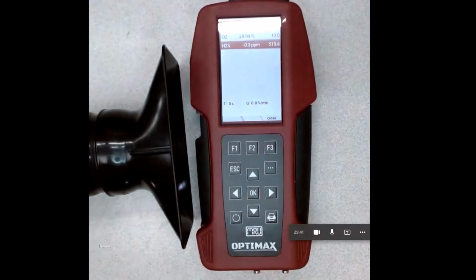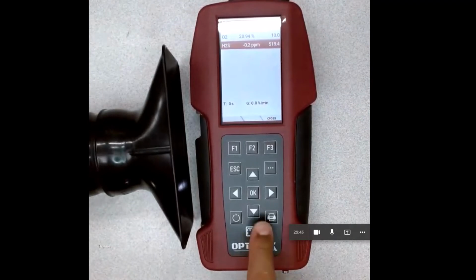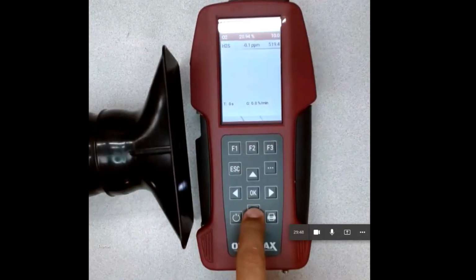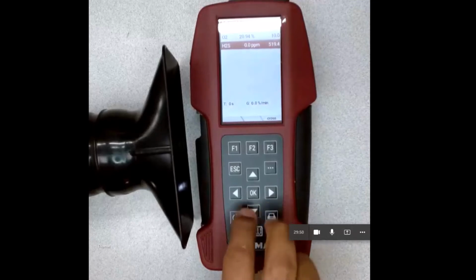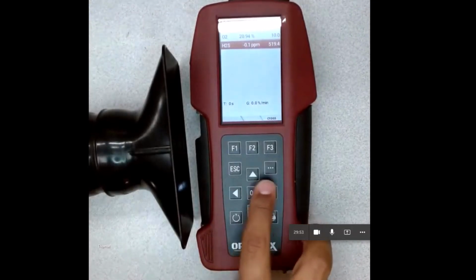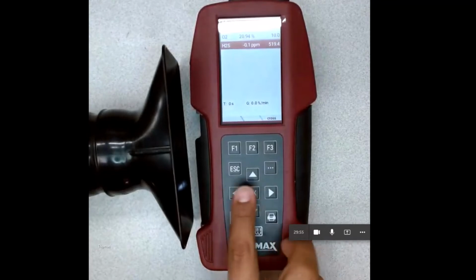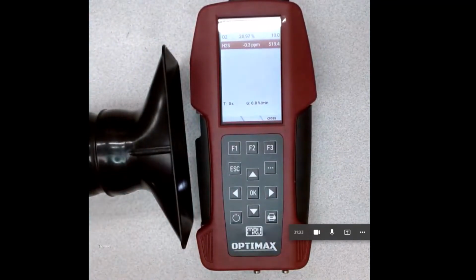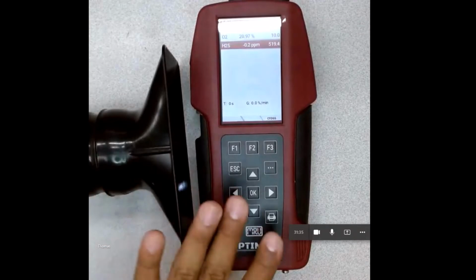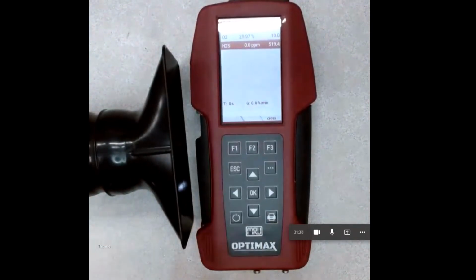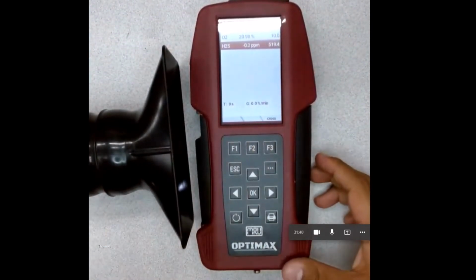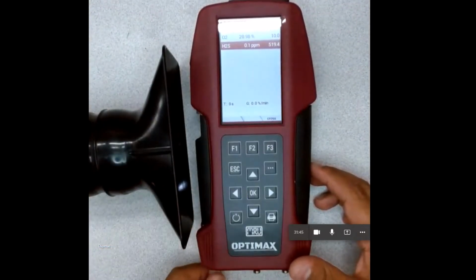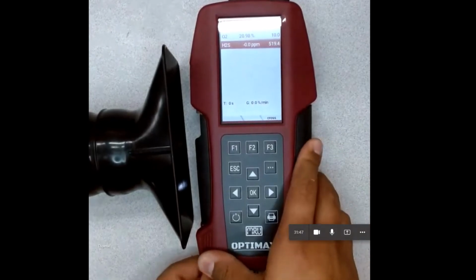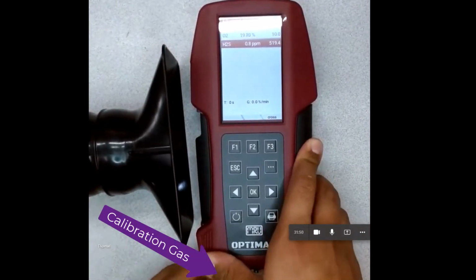So to adjust the cylinder values, or the nominal values for the gases, all you need to do is navigate to each individual gas with the up and down arrows, and then adjust the values up or down with the right and left. Okay. And since we're in this menu right now, we have the 0. We can start sampling gases. So I'm going to connect this hose that has my gas into the gas inlet on the bottom of the condensate trap.